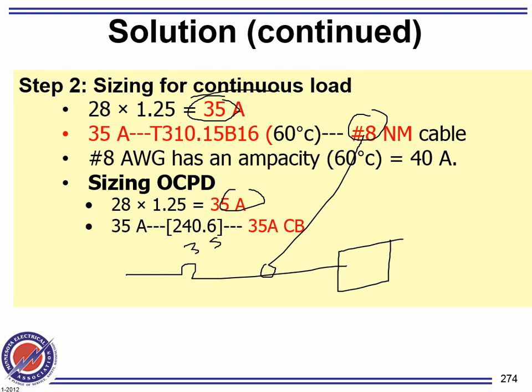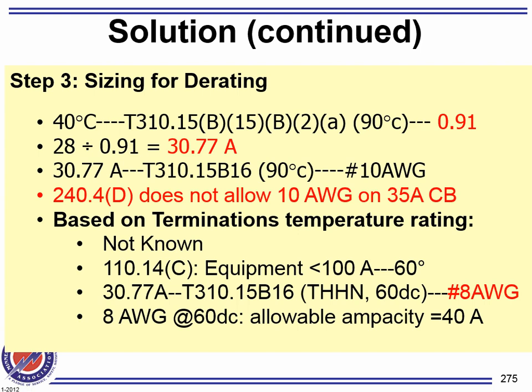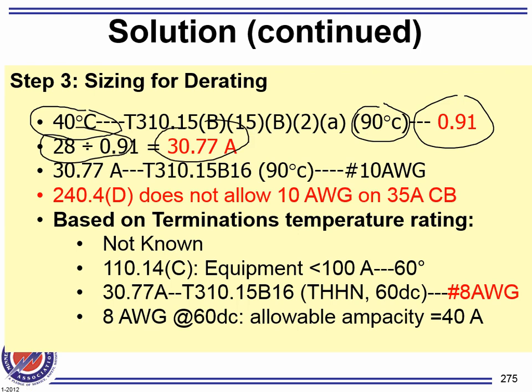Romex, guys, if you go to the 334.80 Romex, it tells you it's the worst of the worst. So regardless of the size and the lug, you must always go to where? The 60 degree column. Now we size this, we put it aside. Now we need to size the conductor based on bundling. Based on bundling, gentlemen, these heating panels are considered to be operating at 40 degrees Celsius. Based on the 90-degree column, they'll get you 0.91. If you take the 28 divided by 0.91, that gives you almost 31. Under the continuous table 310.15(B)(16), you go to 90, and they give you number 10.